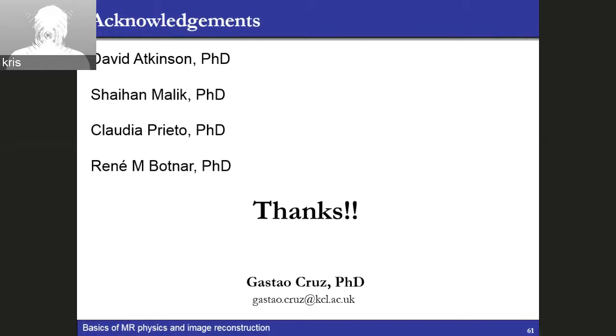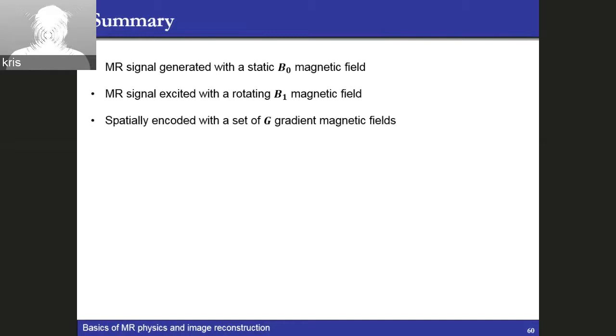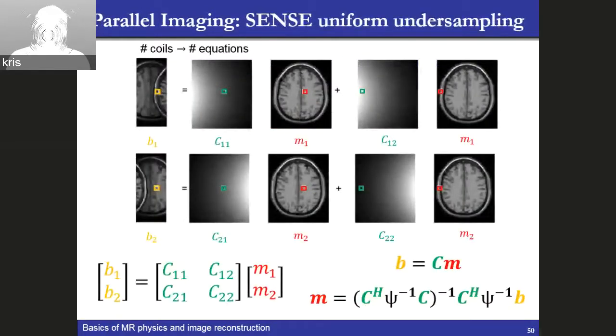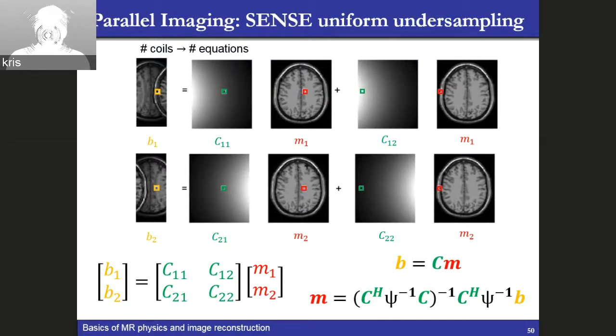Going back to the slides and coil sensitivity: for reconstruction, you need the coil sensitivity maps. Commonly, before you acquire your undersampled k-space, you do a small calibration scan — acquiring a low-resolution set of images from which you can estimate the coil sensitivities. You do this once at the beginning of your scanning session, and then you can use these coil sensitivities to reconstruct all different types of images with different accelerations and contrasts.